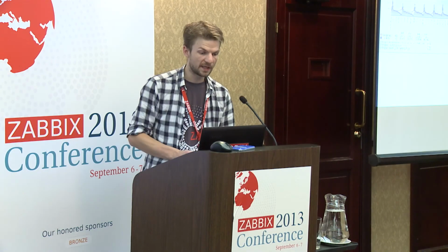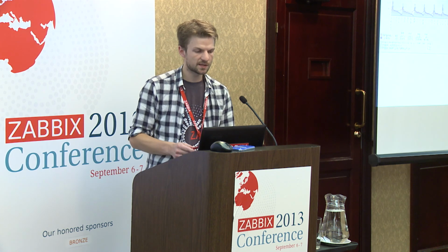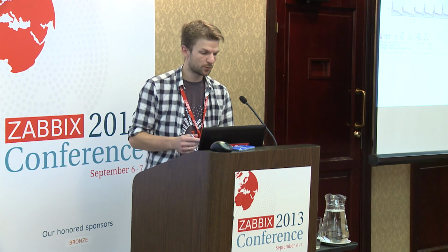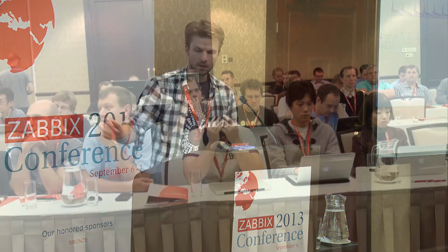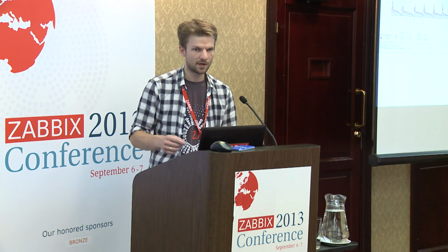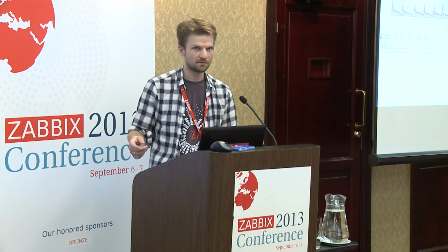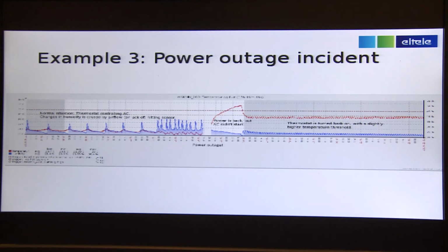The first half of the graph, from left to middle right, is the current baseline. That is a normal situation. We see some fluctuating. Temperature is gradually rising a little bit, going down, up, down, down, and that's normal, as well as the humidity. Humidity is a bit more violent. But these readings are due to the thermostat kicking in, cooling down, being satisfied, and then turning off. So hence this pattern.